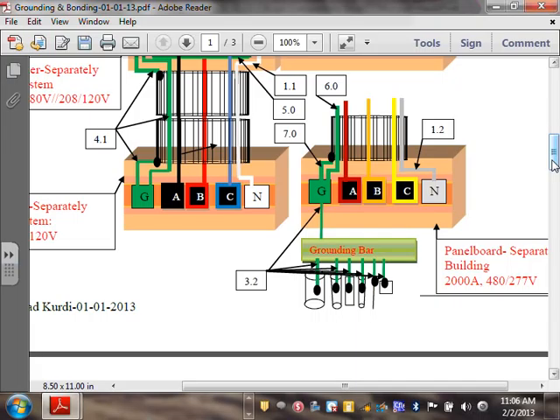Except if that one was a water pipe or a ground rod, then you have to supplement it with another one. That's why we end up, guys, most of the time with two, water and ground rods, in the second building at least. If your building is a concrete building, then you tie to the rebar if you have access to it. So you really do the grounding electrode system exactly as if it's a new service. Same thing, as if it's a new service. The only thing you don't do, can you guys see the bonding between the neutral and the ground? No bonding between the neutral and the ground. So that's the only thing you don't do, exactly like a service.